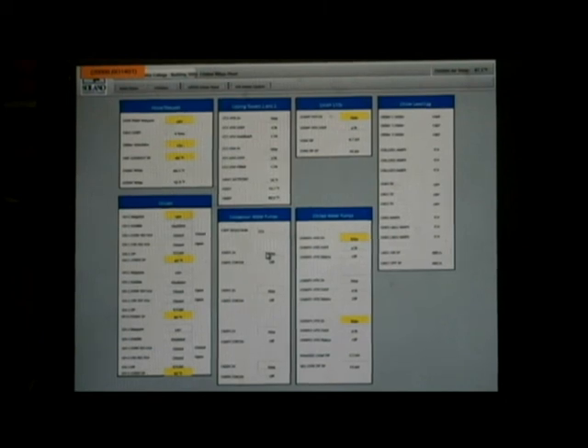It's been proven with this system that we need to have at least 2 of these condenser water pumps running. There are no VFDs on these, so we start the lead and whatever lag 1 pump is, so that it can provide enough flow through these chillers without them shutting down on any safeties. Anything less than 2 pumps, we have proven on any of the chillers that they will keep shutting themselves down due to lack of flow going through them. So now we have chilled water pumps and condenser water pumps running. The next thing that happens is our chiller is enabled, and then we pass that through the network.